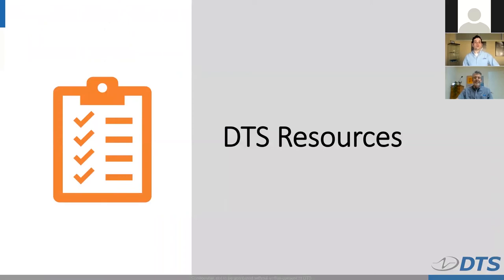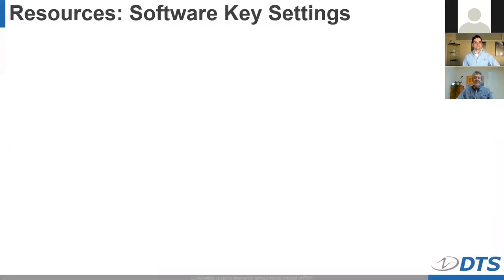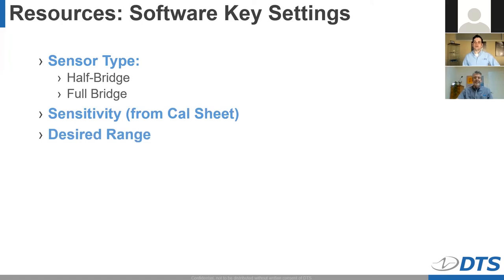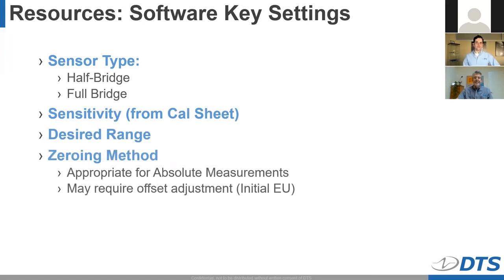Finally, we're going to cover what we recommend you have in mind when selecting and setting up your sensors, as well as what comprehensive materials we have in our help center. When setting things up in software, we make this pretty simple with whatever software package you're using from us — there are type-ins or drop-downs to make sure you're following things accordingly. Make sure you pay attention to your sensor type, sensitivity — you'll probably get this from your CAL sheet — your desired range, and your zeroing method. These first four are the ones you really want to have your eye on when setting things up correctly.